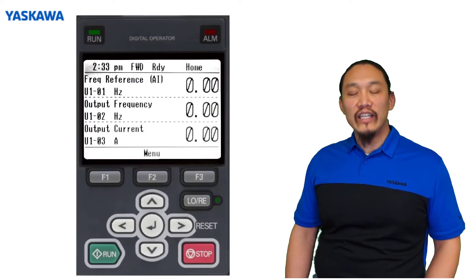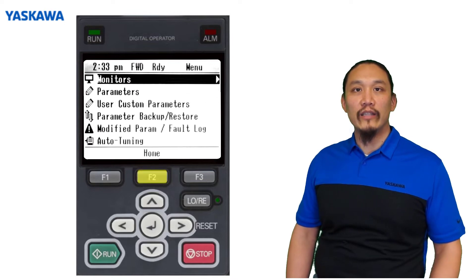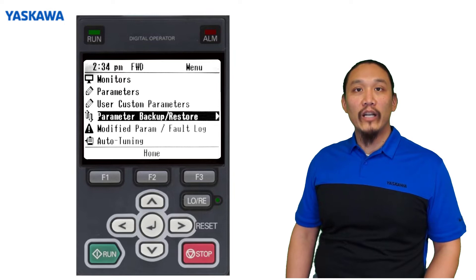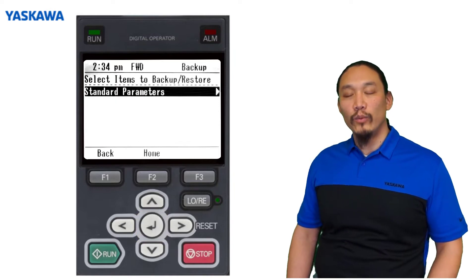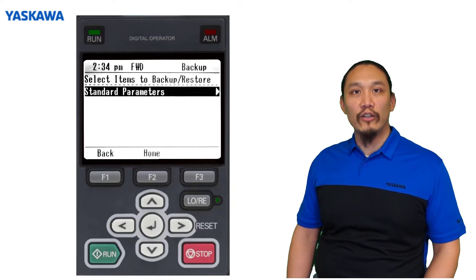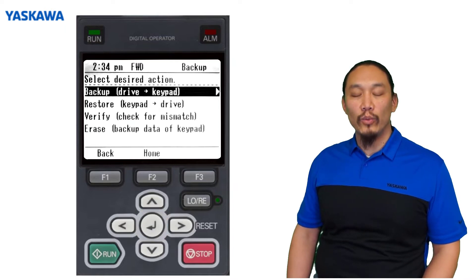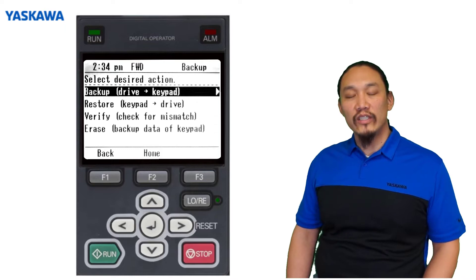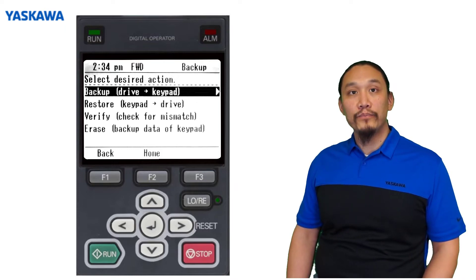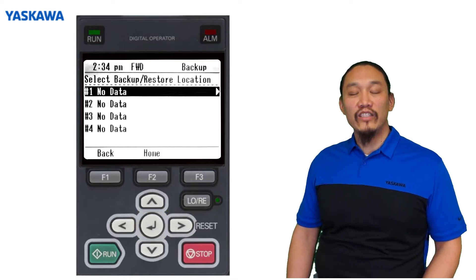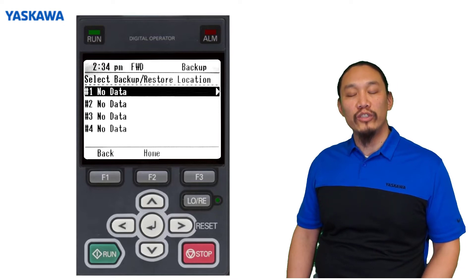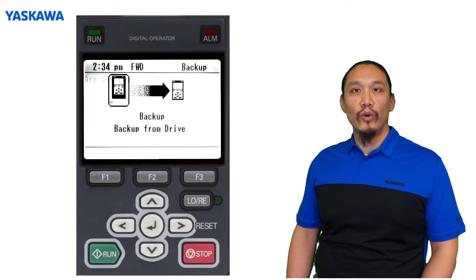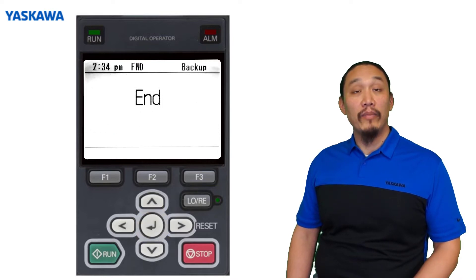As you can see in the example here, a few quick key presses and you're at the parameter backup/restore option. Once you are on the backup/restore menu, you're presented with the option to backup the drive standard parameters. Next, select which option you want: backing up the drive parameters to the keypad or restoring the saved parameters to the drive. When creating a backup, select one of the four available storage slots to put the drive's parameters and press enter. The drive's parameters are now stored on the memory in the keypad. That's it.